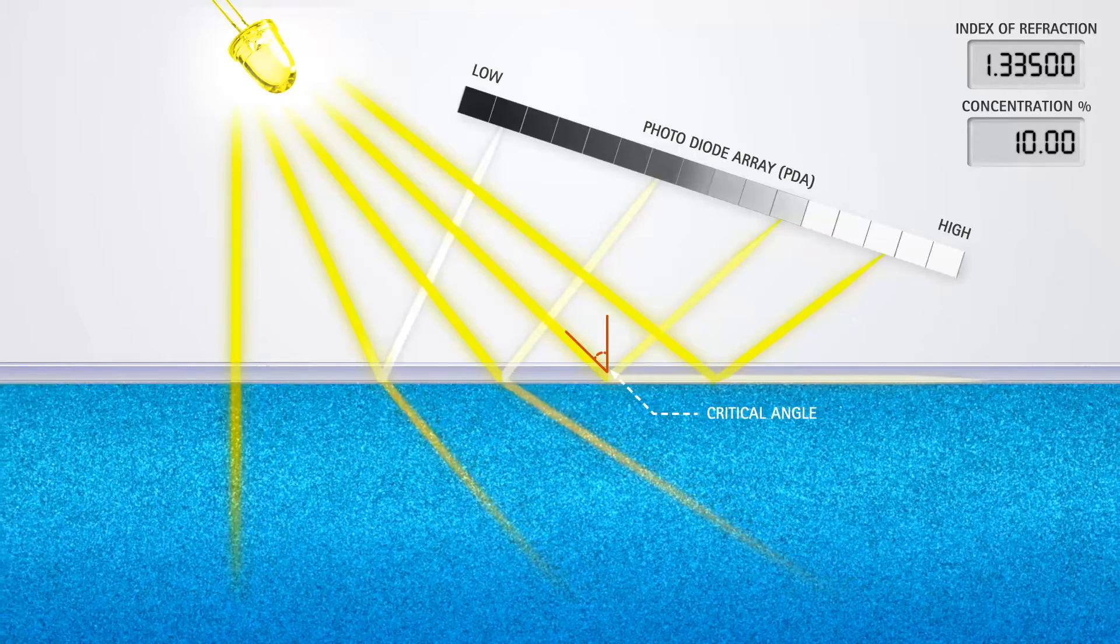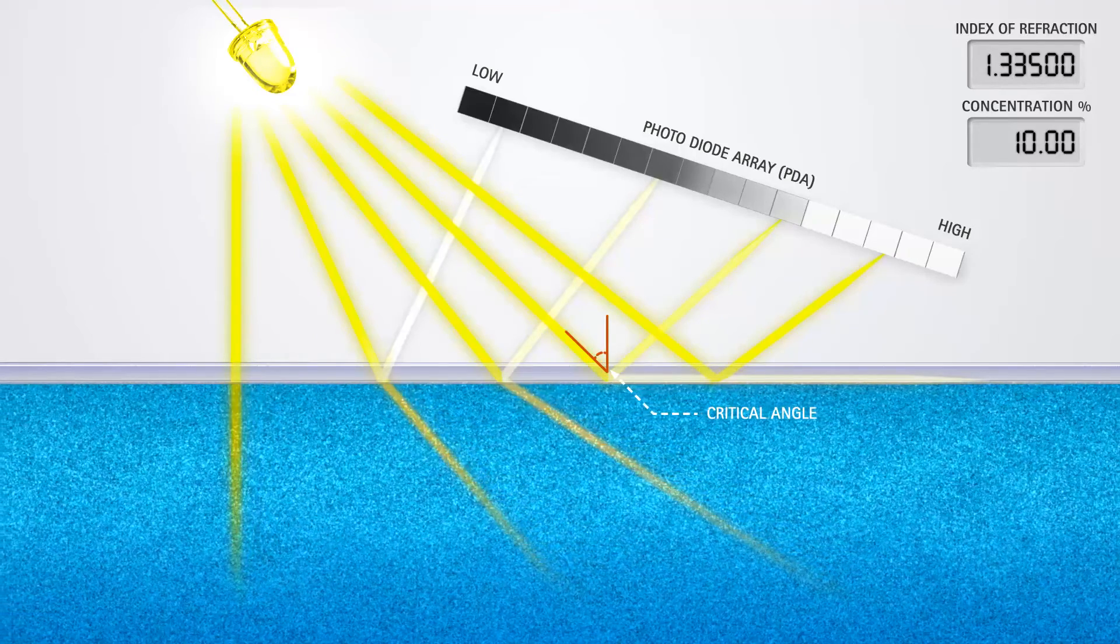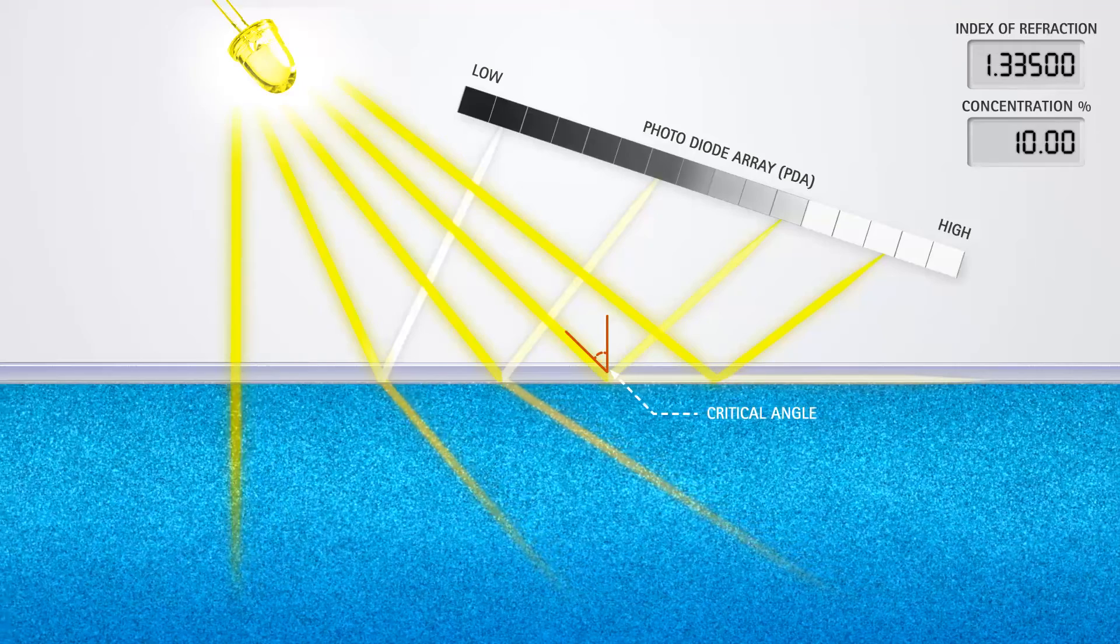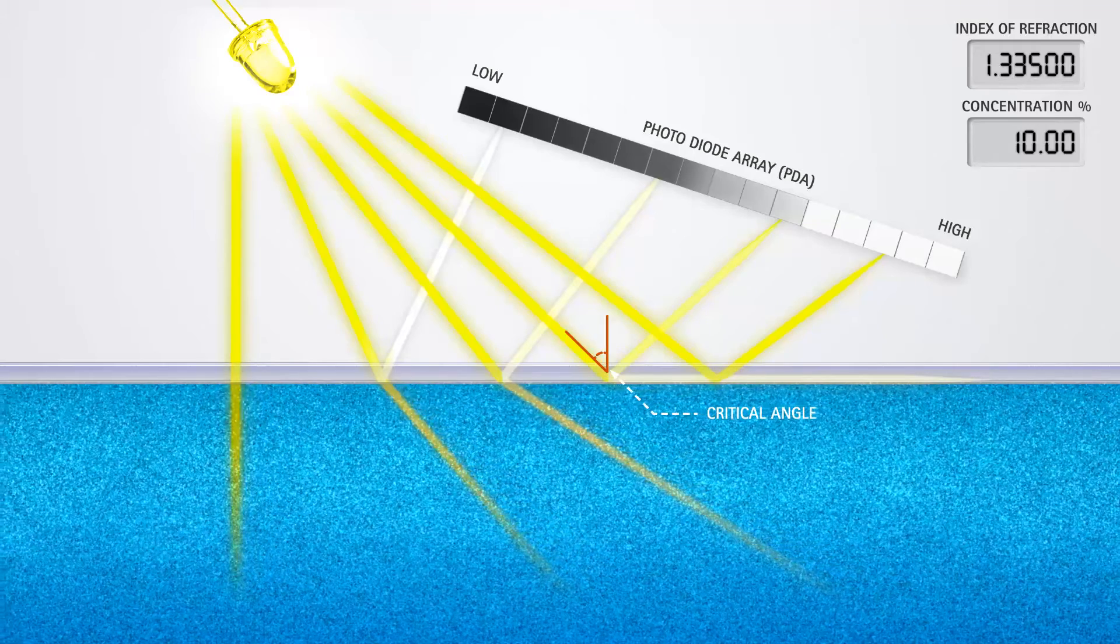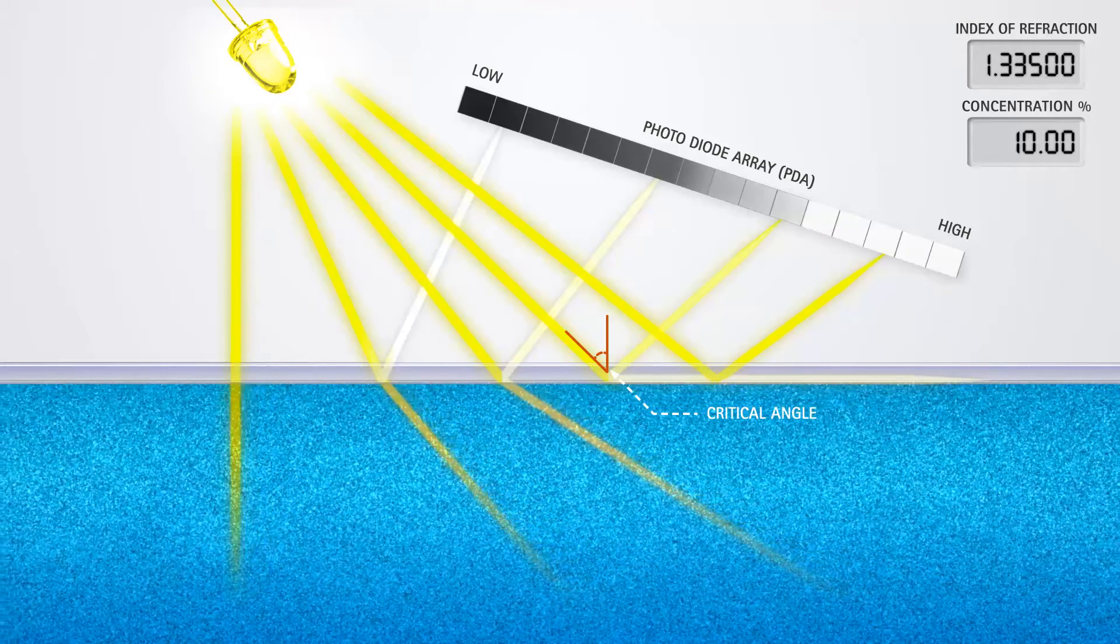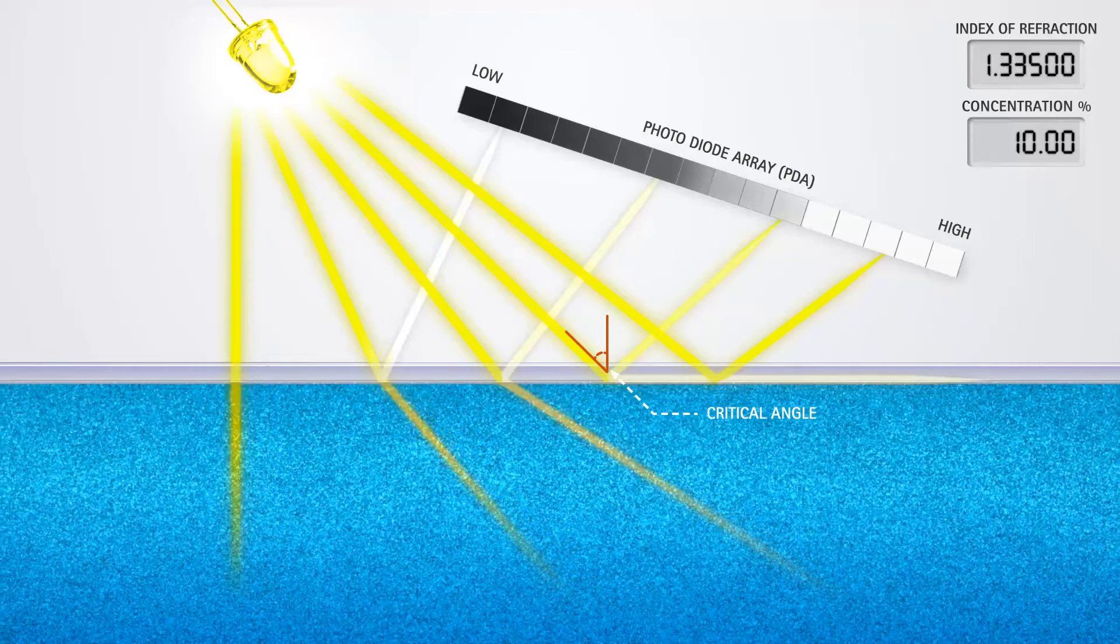Additionally, because Index of Refraction changes with fluid temperature, a thermistor monitors the temperature, and the software compensates the Index of Refraction in real time.